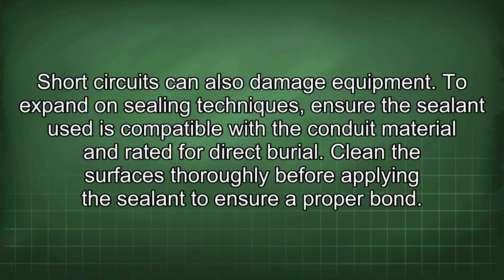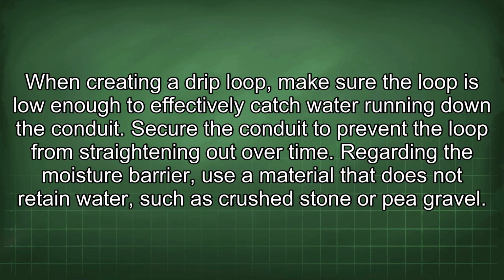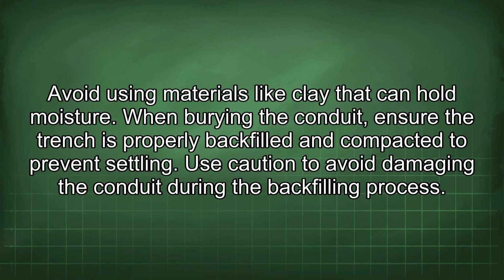To expand on sealing techniques, ensure the sealant used is compatible with the conduit material and rated for direct burial. Clean the surfaces thoroughly before applying the sealant to ensure a proper bond. When creating a drip loop, make sure the loop is low enough to effectively catch water running down the conduit. Secure the conduit to prevent the loop from straightening out over time. Regarding the moisture barrier, use a material that does not retain water, such as crushed stone or pea gravel. Avoid using materials like clay that can hold moisture.